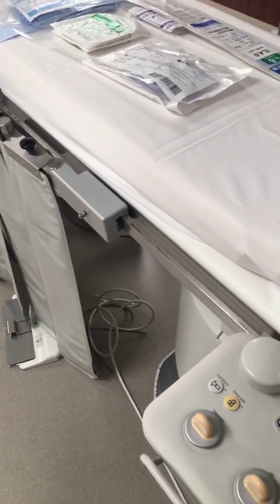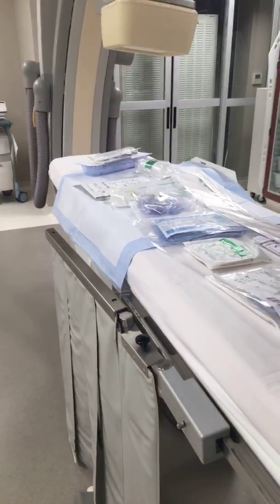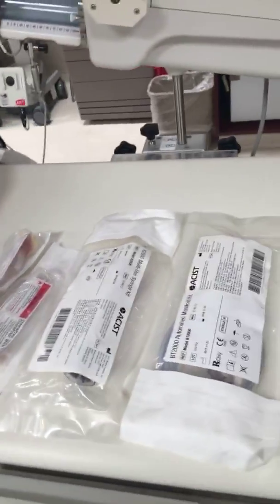Stored, recalled positions. If you want to program a position, and that's the area that the doctor likes, you program that. Then once you're out of position, you just push that automated button here, and it'll go right to that exact position. It's important when you find a lesion that you get the exact image, so you don't have any discrepancies in your approach, or any elongation in the image you're producing from a different angle. The problems could be elongation, foreshortening, and it can give you a false sense of position. We don't want that when we're dealing with a coronary stent, because we're dealing with millimeters. You're off by a portion of a millimeter, and you're into bad tissue. You could cause a rupture or a dissection, or just not fix the area and have a stenotic region form right after.